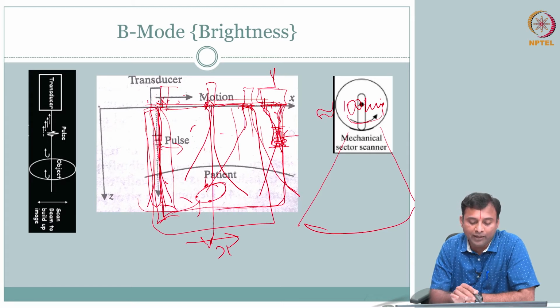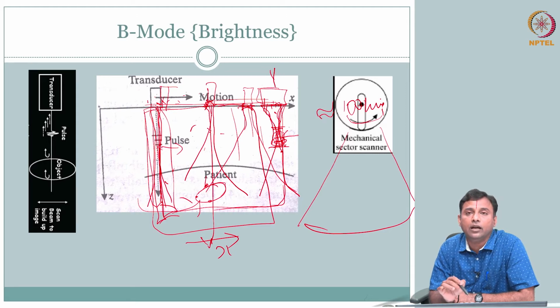But on the other hand, if I have a smaller transducer, then the divergence will be an issue and I cannot have a focusing effect, right? And of course, my step size also should decrease, and therefore the time for acquiring the data is going to increase. So all these trade-offs made it the way it was done until the 90s, for example.